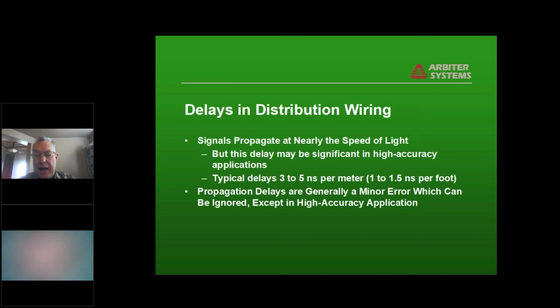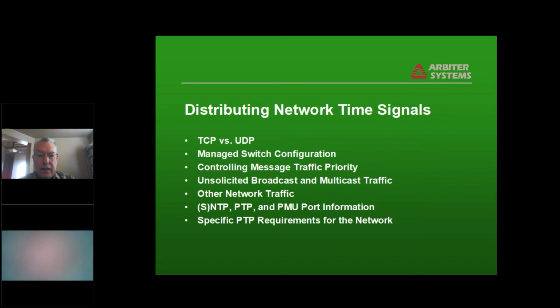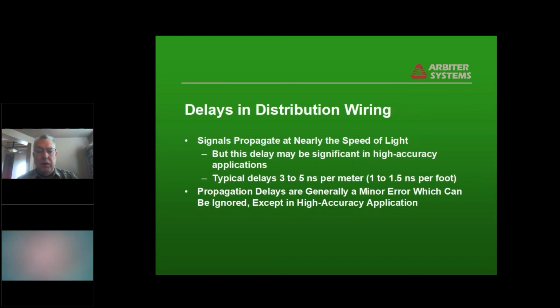And if you're using a high accuracy application like traveling wave fault location or synchrophasors, and you've got a fairly long cable, then the delays can be significant. We provide in our clocks, and I think most other companies now do, the ability to advance the time code that's being transmitted to compensate for the delay in the line. So if you know you have a 100-foot line and it's got 130 nanoseconds of delay, you can set the cable delay number to advance the time code by 130 nanoseconds so it arrives on time at the far end of the line. As I said, that's only really necessary if you're doing something like traveling wave fault detection or synchrophasors or something else where you're trying to get the absolute best accuracy. For recording applications, it's generally not needed.